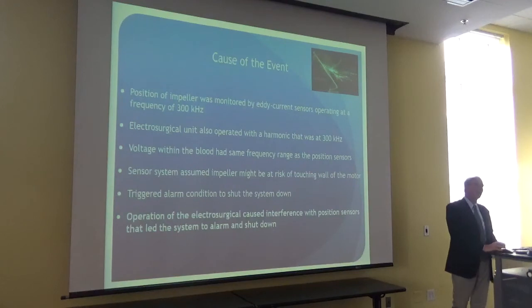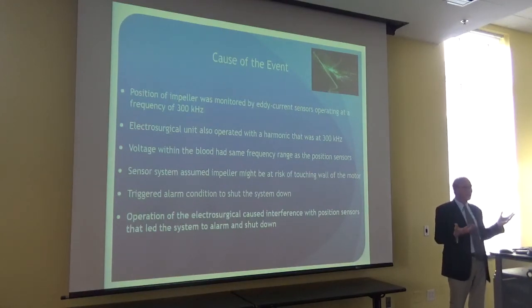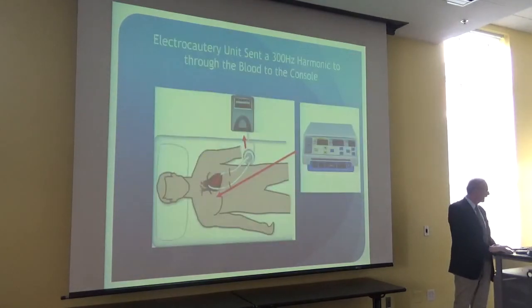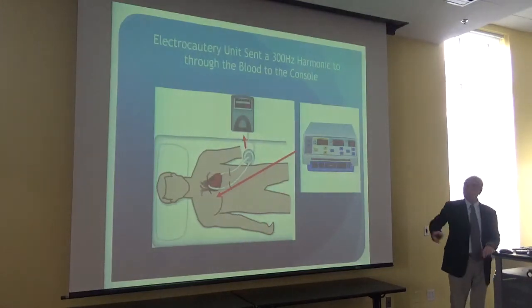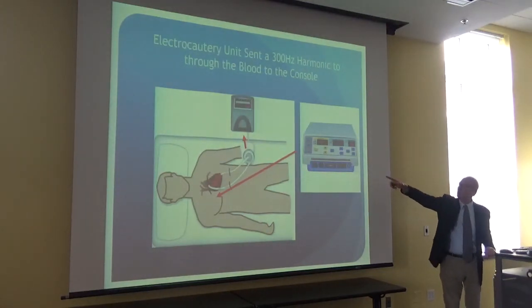Now you may say, well, there's so much rigorous testing that has to go into these medical devices. How could it be possible that you made it through electrical safety and you didn't catch this? So this just illustrates what we're saying. This is the electrocautery unit. It was being used on the patient. It was picked up and transmitted by the blood to the pump, the motor, and then ultimately.